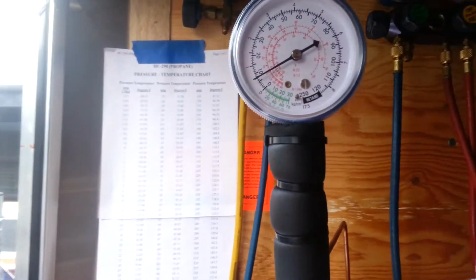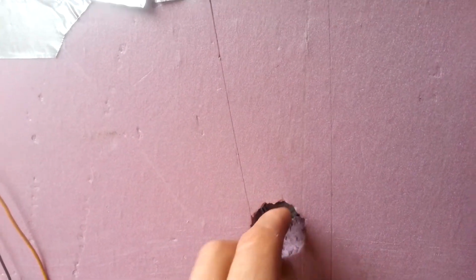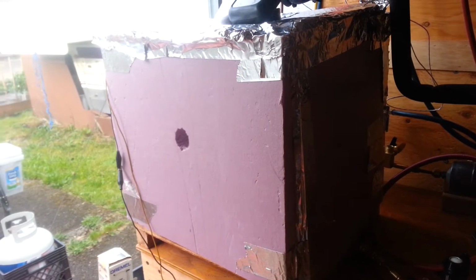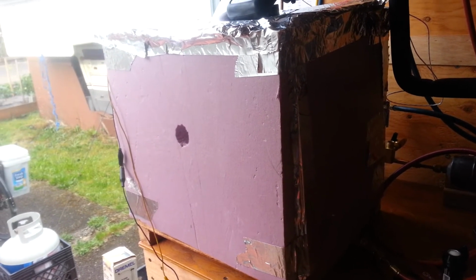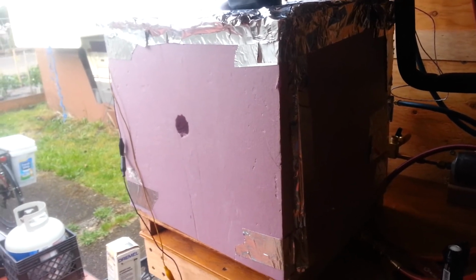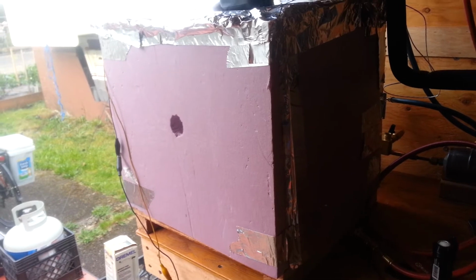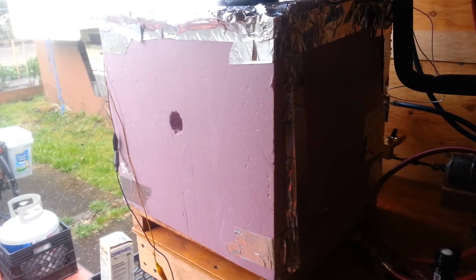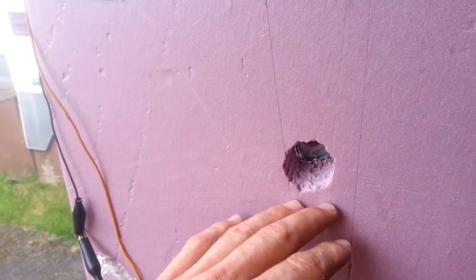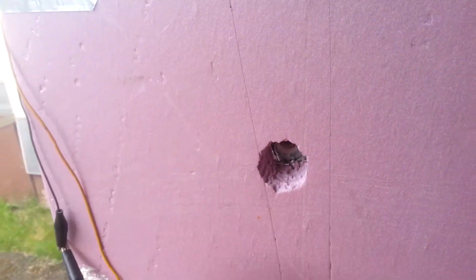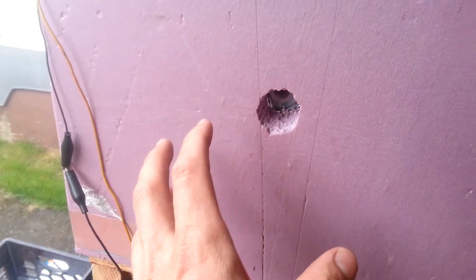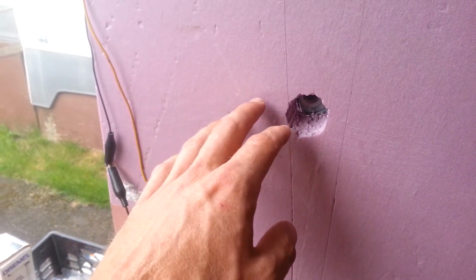At those lower pressures and temperatures associated with it, there's a hell of a lot more of a delta T, temperature difference, that is, between the evaporator coil and the contents of the box, whether it is cooling beer, or cooling the air, whatever it happens to be. And when there's a larger temperature difference, the ebullition, the boiling, that is, of the propane refrigerant inside the coils will occur in a more violent manner, and that refrigerant, as it boils over, comes up the coils themselves and carries liquid out over. Even though it might be in somewhat of a dry condition, the liquid level that's maintained, even though there's a lower mass of actual liquid within the coils themselves, the activity continues to be maintained.